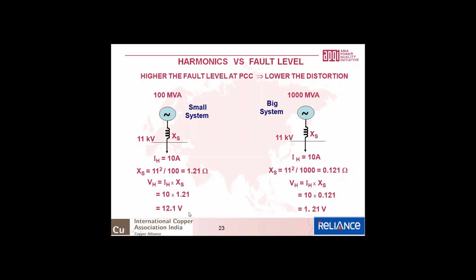Whereas the same harmonic current of 10 amps in a big system, where the system fault level is 1000 MVA, sees a system impedance that is now 1/10 of 1.21, 0.121 ohms. Therefore, the harmonic voltage the 10 amps creates is 1/10 of what is created in a 100 MVA system. Naturally, when you go to higher and higher voltage levels, the fault levels go higher and higher, and that is the reason why the effect of harmonics at higher voltage levels is not as serious a concern as it is in low voltage systems.